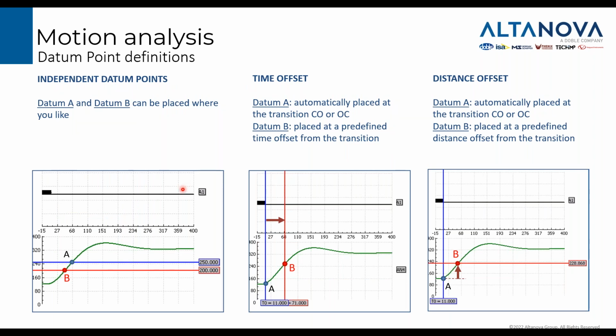These 2 points can be defined in different ways. The 2 points can be independent of each other, so the operator decides where to put them, but this is not the most used approach. The most used is to set the point A when the main contact changes status, and the point B with an offset. It can be an offset in time, or an offset in distance. In this way, you are sure to get the measurement in a reliable way, because at least point A is defined automatically, and point B as well, because you are just defining an offset. You don't have to remember the absolute position of the two.